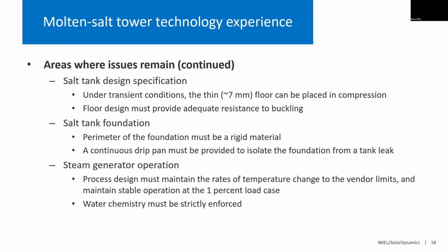These tanks are typically designed to API 650, which is a standard for field-fabricated welded tanks with a flat bottom and a domed roof, typically for oil storage. For API 650, there's a limit on design temperature of 260 C. So typically they'll marry allowable stresses from Section 2 of the code with API 650 to come up with a tank design, which is okay, but oil storage tanks tend to be isothermal over the course of the year. They don't change much in terms of temperature. And that's not the case for a CSP plant.